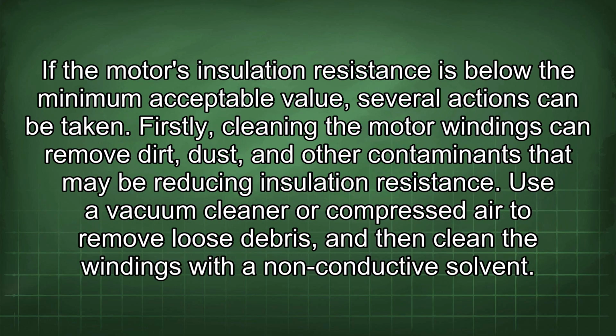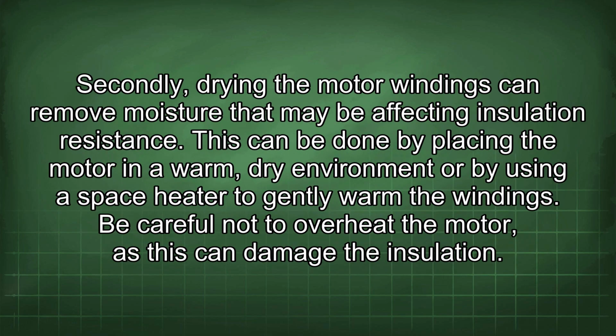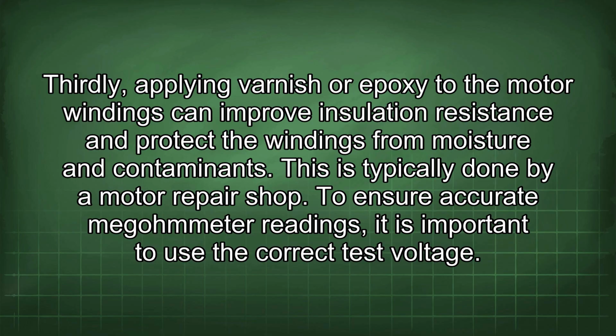If the motor's insulation resistance is below the minimum acceptable value, several actions can be taken. Firstly, cleaning the motor windings can remove dirt, dust, and other contaminants that may be reducing insulation resistance. Use a vacuum cleaner or compressed air to remove loose debris, and then clean the windings with a non-conductive solvent. Secondly, drying the motor windings can remove moisture that may be affecting insulation resistance. This can be done by placing the motor in a warm, dry environment or by using a space heater to gently warm the windings. Be careful not to overheat the motor, as this can damage the insulation. Thirdly, applying varnish or epoxy to the motor windings can improve insulation resistance and protect the windings from moisture and contaminants. This is typically done by a motor repair shop.